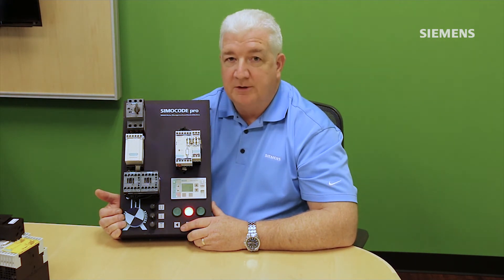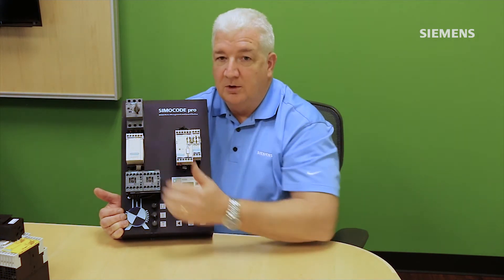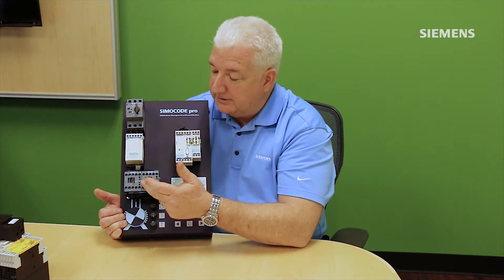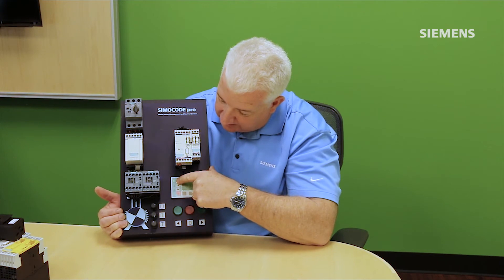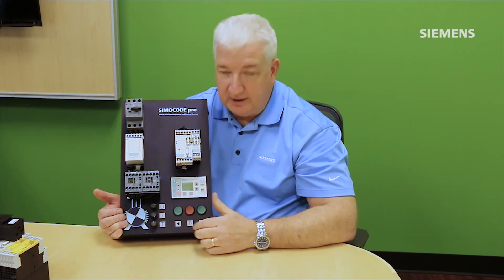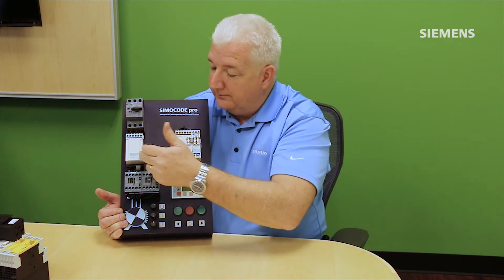SIMOCODE also has a function called TPF — Test Position Feedback — which I refer to as a dry run condition. In normal mode, confirming the contactor closed and motor current flowing indicates a good start. In TPF or dry run mode, it's the opposite: when the contactor closes, SIMOCODE does not want to see motor current flowing. On this demo, pressing and releasing the top operator button initiates TPF mode, indicated by a flashing stop light. You can then disconnect three-phase power and test the SIMOCODE logic.